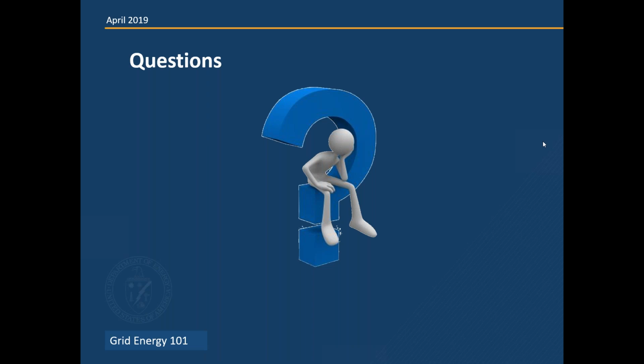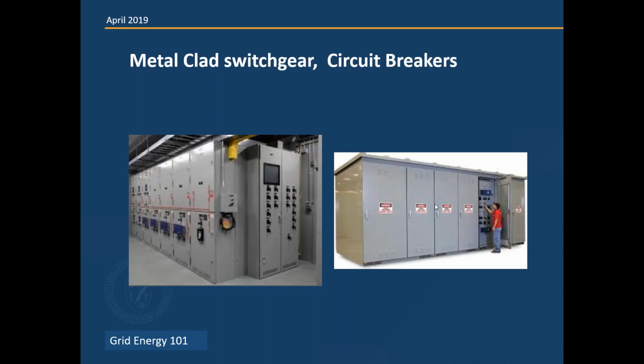Yeah, metal-clad switchgear a lot of the times is used on the 4 kV system at industrial customers. It has the substation bus work in there, and the circuit breakers, and the metering and the protection. So it's a very neat, compact way to put a lot of equipment, but it's more for industrial types of customers. Or you'll find those in power plants if power plants have feeders in there. They have circuit breakers just like those examples of air circuit breakers we saw in the switch yard. It's a way to stuff a lot of equipment in a short, compact area, and it's insulated so you can have multiple breakers in a small area. Gotcha, great, thank you.